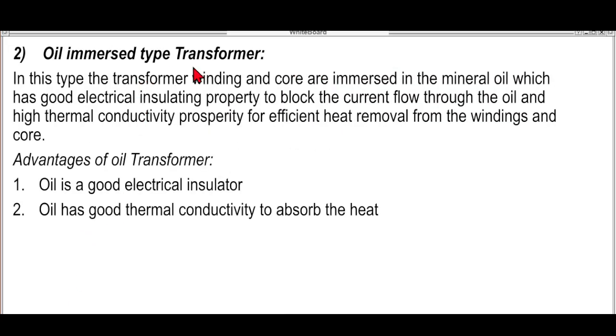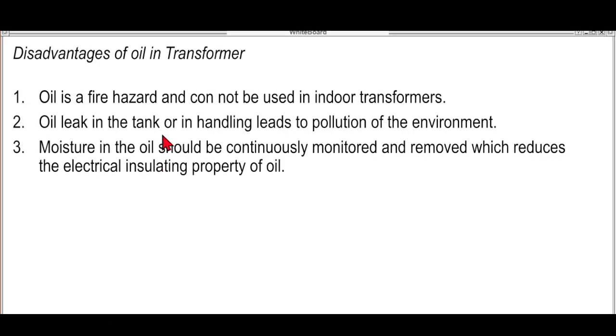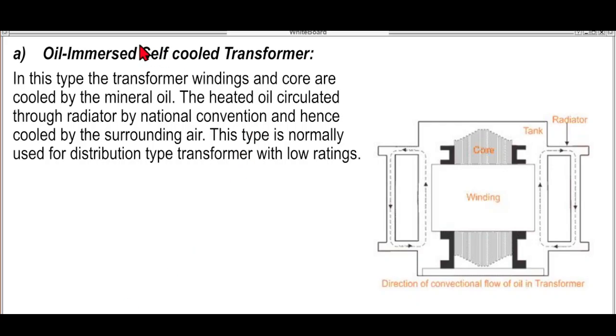Then oil immersed type transformer. So in all of these transformers, the core and the winding itself are immersed, nakalublob sa oil. So oil is a good electrical insulator and it can also absorb heat. So meron siyang good thermal conductivity. Disadvantages of oil in a transformer: pwede siya maging fire hazard. It could leak from the tank and cause pollution. And the moisture in the oil should be continuously monitored and removed para hindi po maapektuhan yung insulation ng mismong transformer.